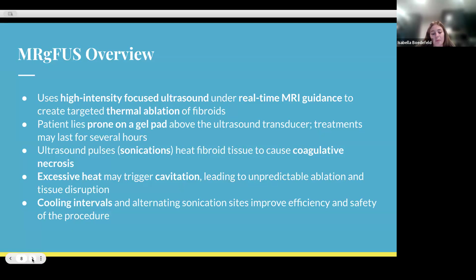And the procedure uses ultrasound pulses called sonications to heat the fibroid, essentially killing the fibroid cells without surgery. But if the temperature gets too high, it could cause cavitation, which is the formation of microbubbles that could lead to unpredictable tissue damage or less precise ablation. And to manage this, the system uses cooling intervals between sonications and alternates treatment locations to allow for time for the tissues to recover.